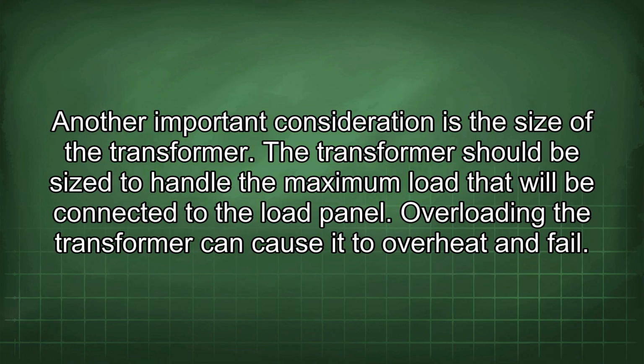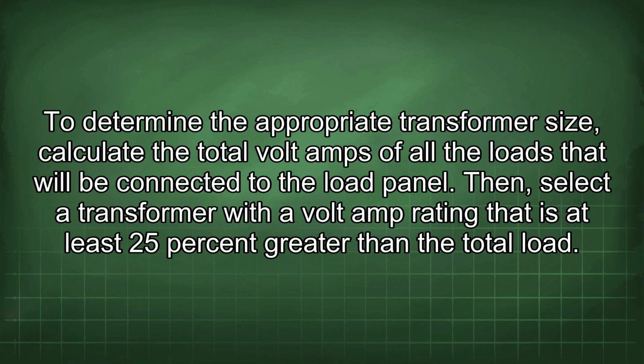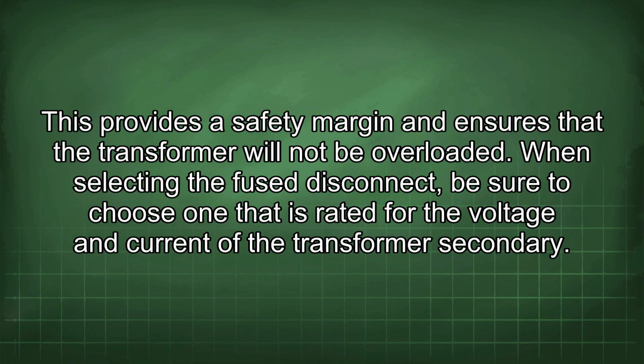Another important consideration is the size of the transformer. The transformer should be sized to handle the maximum load that will be connected to the load panel. Overloading the transformer can cause it to overheat and fail. To determine the appropriate transformer size, calculate the total voltamps of all the loads that will be connected to the load panel. Then select a transformer with a voltamp rating that is at least 25% greater than the total load. This provides a safety margin and ensures that the transformer will not be overloaded.